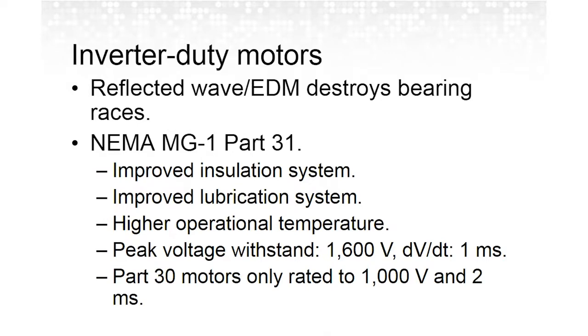And again, with the fast switching IGBTs that we expect to see used with pulse width modulation, the fact that they can turn on and off real quick sort of exacerbates the reflective wave phenomenon, and you can have transients which exceed 1,000 volts. So basically what MG1 does is say that the motor has to withstand transients of 1,600 volts with a rise time of 1 millisecond. In addition, oftentimes you will see standard options such as shaft grounding rings.